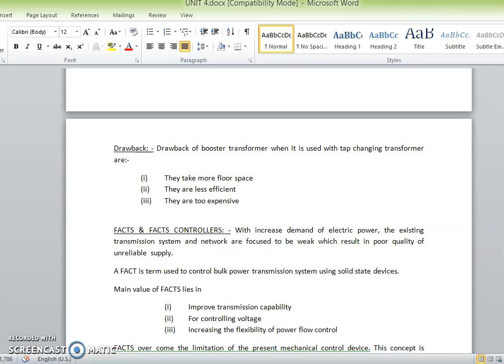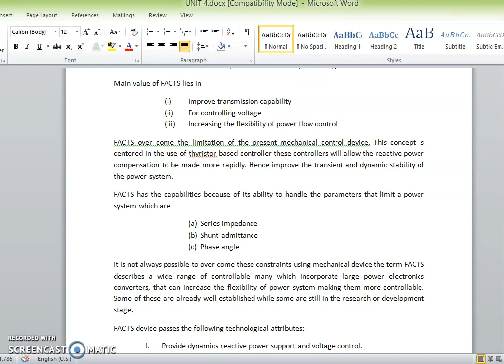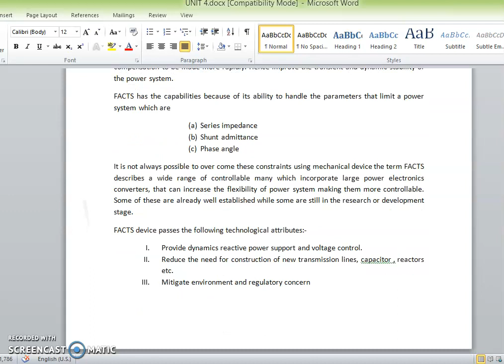These concepts centered on the use of thyristor-based control. These controllers allow reactive power compensation to be made more rapidly, hence improving the transient and dynamic stability of the power system. FACTS has this capability because of its ability to handle the parameters that limit a power system, which are series impedance, shunt admittance, and phase angle. It is not always possible to overcome these limitations using mechanical devices. The term FACTS describes a wide range of controllers that may incorporate large power electronic converters that can increase the flexibility and control of the power system. Some of these are already established.